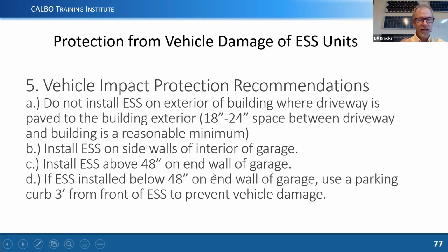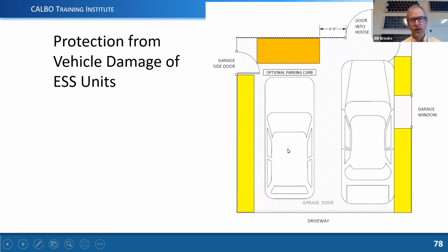We can install the ESS on the sidewalls of the interior garage, and we can put it on the end wall of the garage as long as it's 48 inches off of the ground. If we're below 48 inches off the end wall, then we can use parking curbs and other things. There are a few different versions of that, but here's an example of inside a garage.